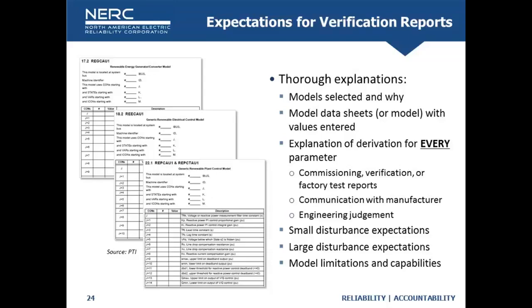You can show communications with the manufacturer, the equipment owners. So asking questions about, well, why are these parameters set the way they are? Provide me an explanation of why they are set that way. And maybe in some cases you're using engineering judgment for parameters like measurement time constants, things that are more standard. You can use engineering judgment for that. So from the combination of all those, you should be able to describe what every parameter is and why. It doesn't necessarily mean you have to apply a fault or apply a step change and demonstrate a match, but you should be able to show verification in other forms.